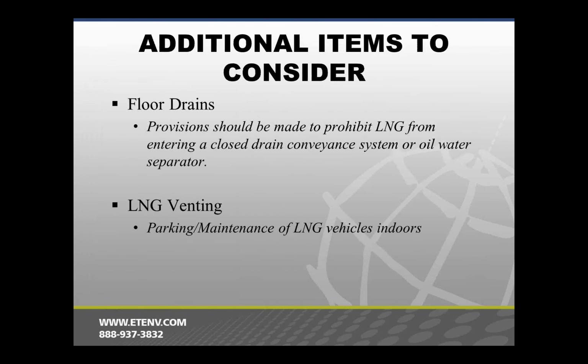So a few other odds and ends. If you have LNG in the shop, you need to be careful of that LNG entering a closed drain system, if you have floor drains in your shop or oil water separators or sump tanks, because LNG expands 600 times when it vaporizes and can act more like an explosion during a rapid vaporization if it were to come in contact with water. So it's just something to be aware of.